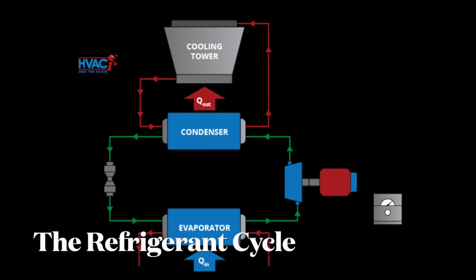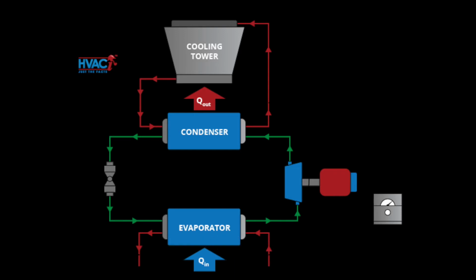The refrigerant cycle is taking place within the chiller itself, and it is a closed loop system. The refrigerant, a chemical, starts out in the evaporator and then makes its way to the compressor. When in the compressor, it moves to the condenser, and finally into the expansion valve.